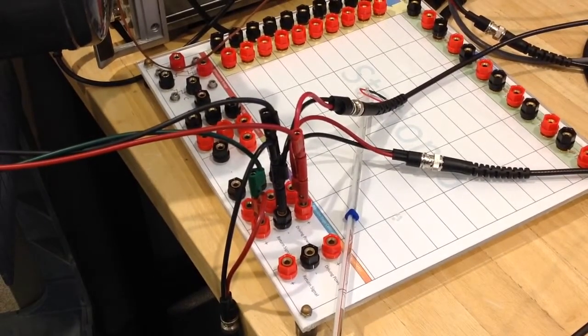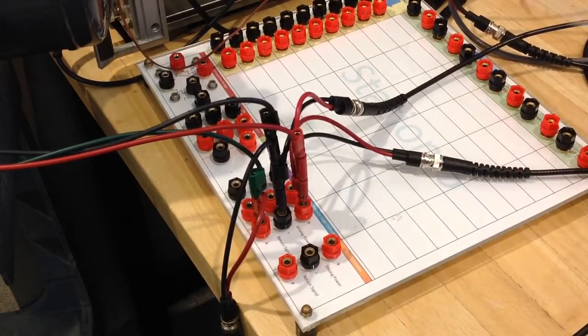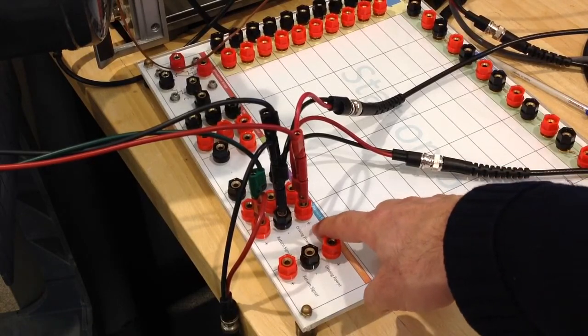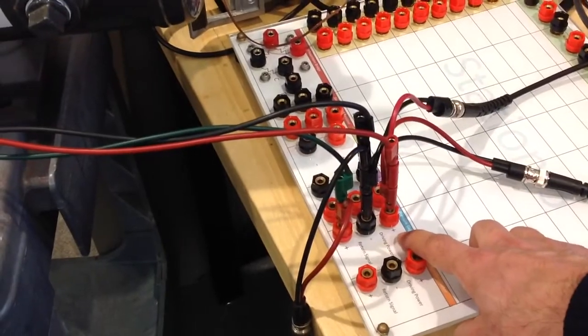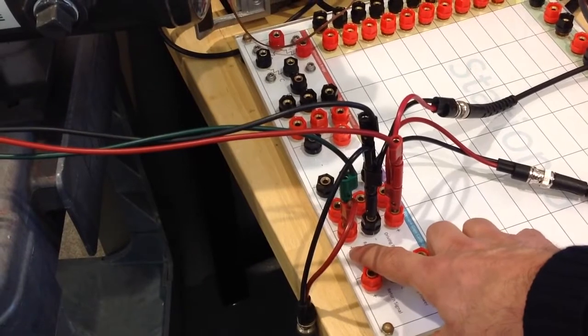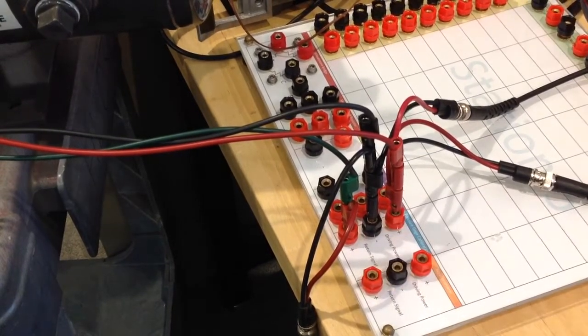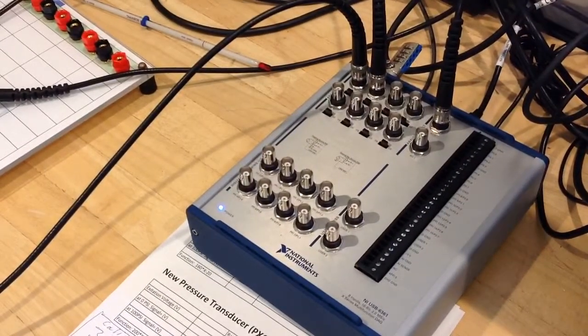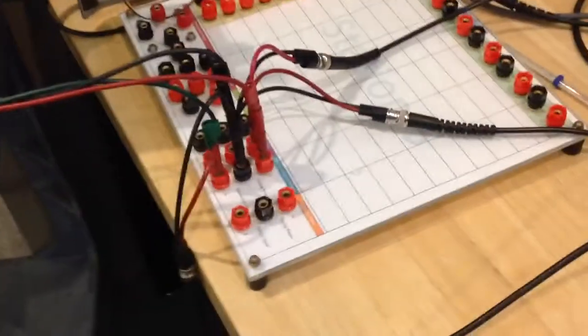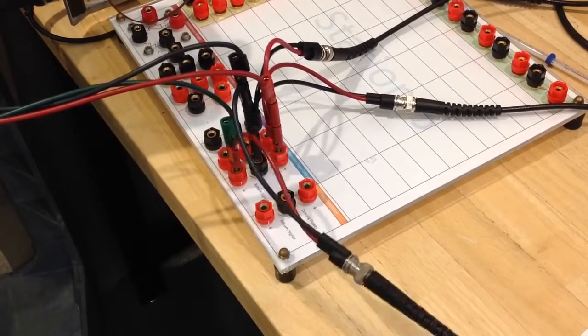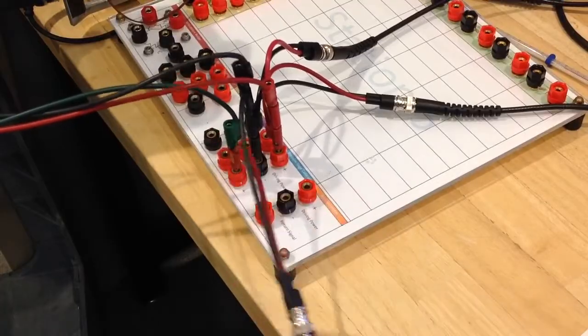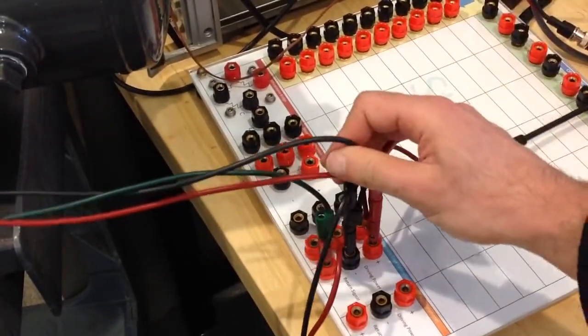So now these are all connected to the connectivity board, which has the pressure gauge calibration section here, okay? So it has a plus terminal for the driving voltage, which is the excitation voltage, and then a terminal for the ground, a terminal for the return signal from the pressure transducer. And these are connected to the DAQ board here. So analog output goes to the driving power here, and then I read with 2 channels on the DAQ board. So the first channel here reads from the sensor. Okay, so AI0 reads from the sensor, and AI1, which is here, it is reading the excitation voltage. Okay, so this is the setup.